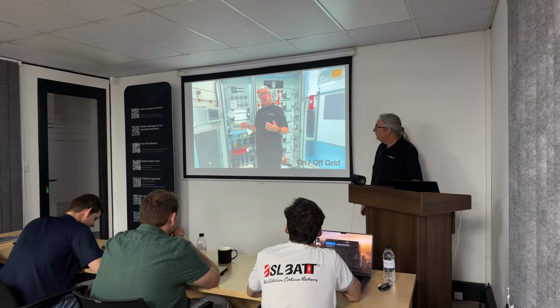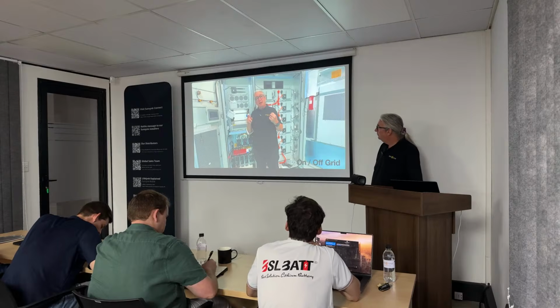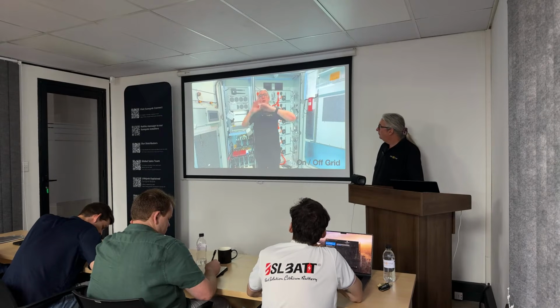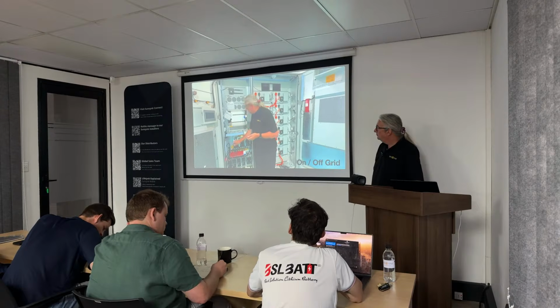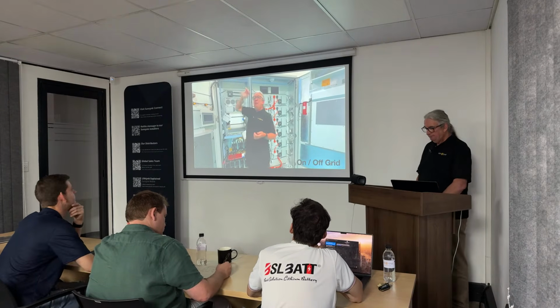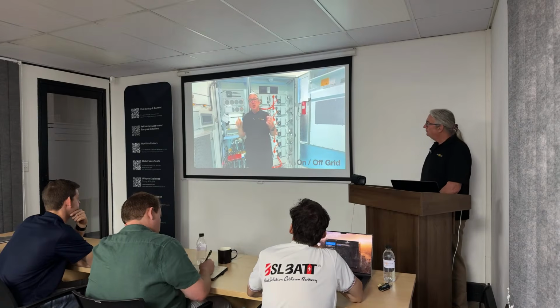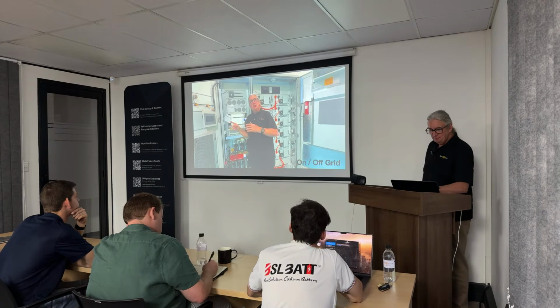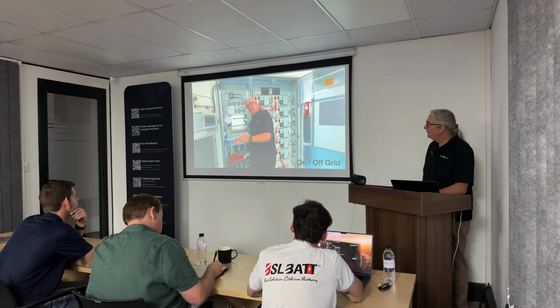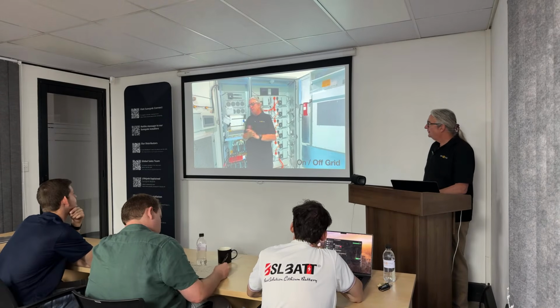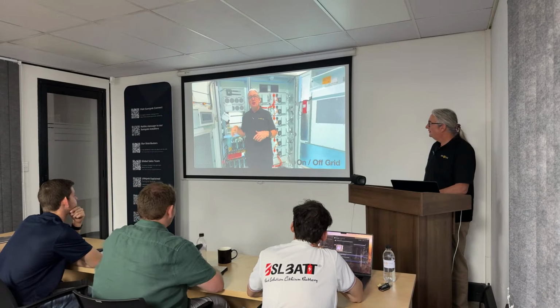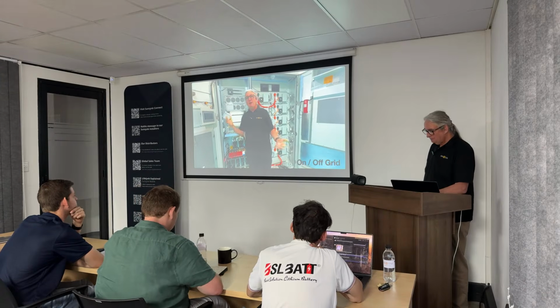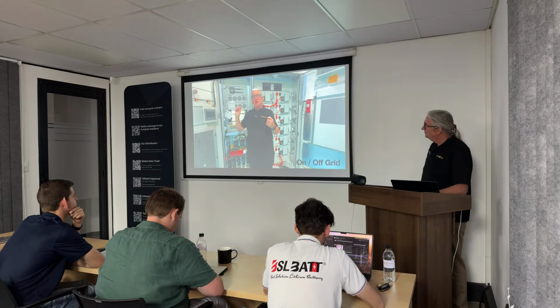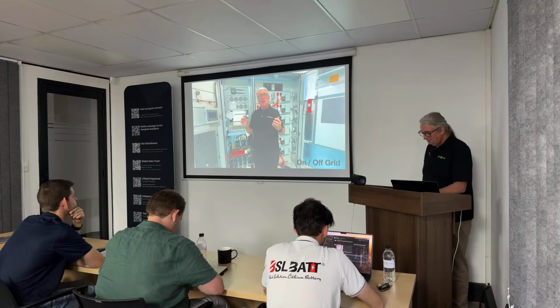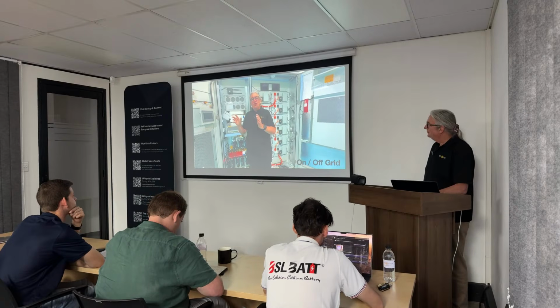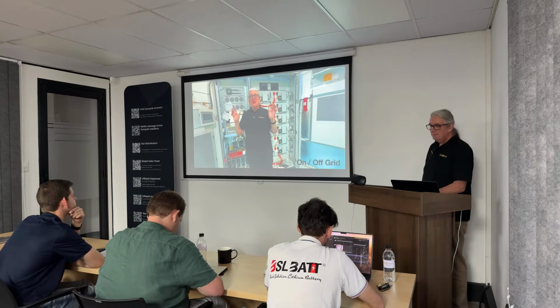And this one is actually the generator input, but this is a direct connection. You have to physically switch, you have to override it. It's done by a breaker. What we intend to do is connect this unit here, on the top here, we're going to fit an additional PCS. So the generator port connects directly to a secondary PCS that connects directly to the DC bus. Why would we do that? Simple. That means if the generator runs at, say, 45 or 48 hertz, or the frequency is unstable, it will still charge the batteries. And amazingly, you can run the grid and the generator at different frequencies at the same time.